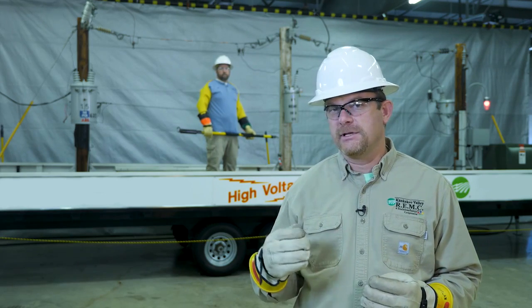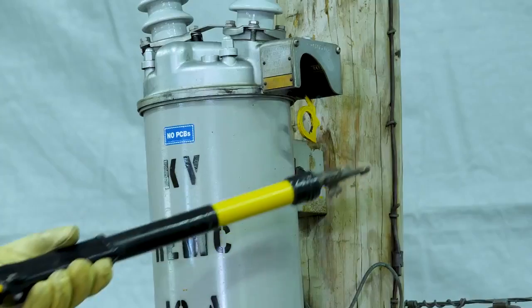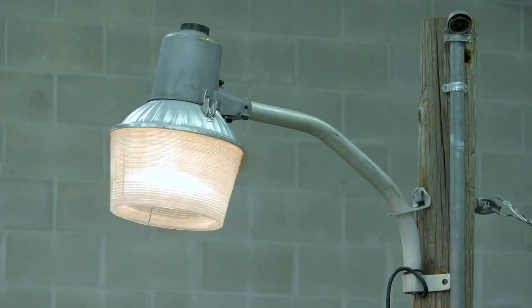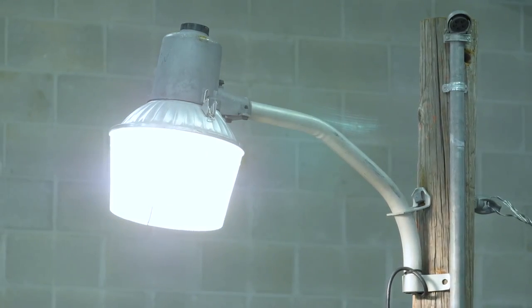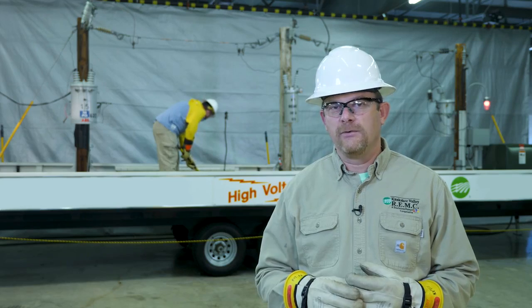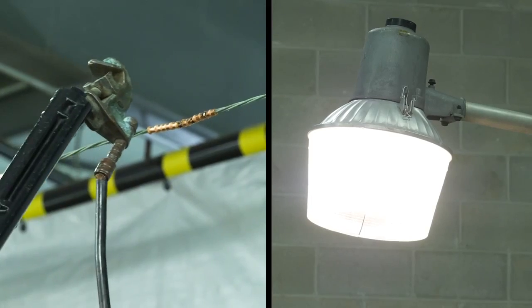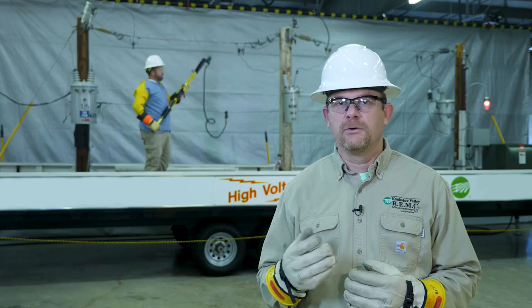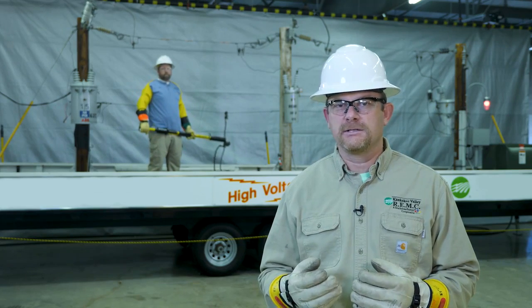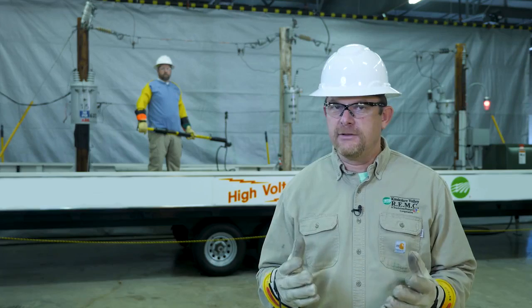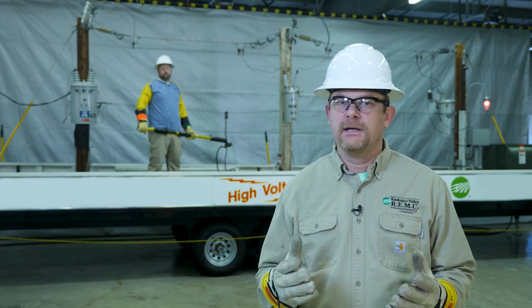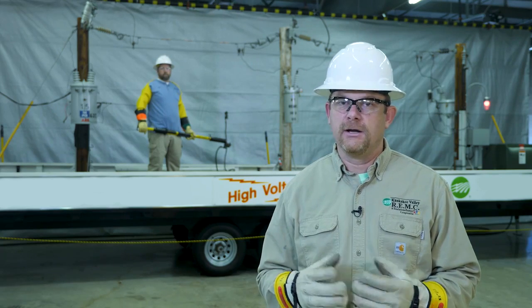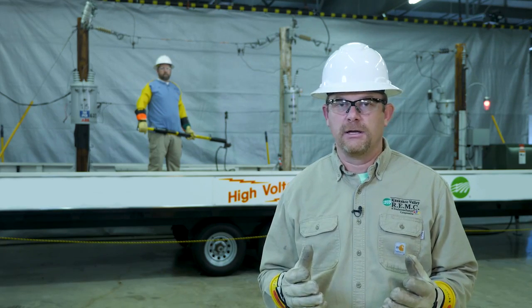Instead of having a fuse in the center cutout, Jeff will close in the yellow handle on the side of the recloser. And notice a light on the meter pole is energized. Jeff will now use a ground cable to create a fault. The recloser is trying to allow the cause of the fault to clear itself. When the recloser does completely break the circuit, the handle on the side of the recloser will drop down. Even though the blinking of the lights may be inconvenient, it can eliminate an extended outage, and it also shows that our equipment is working correctly.